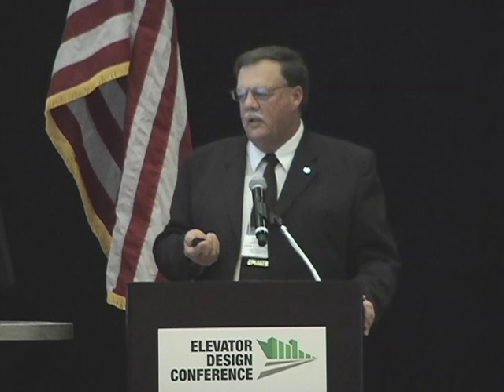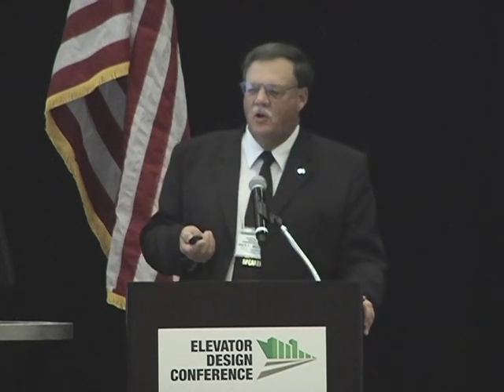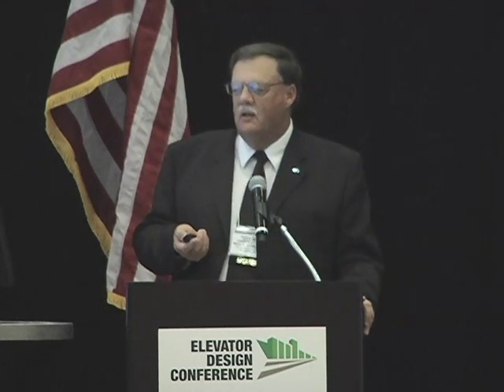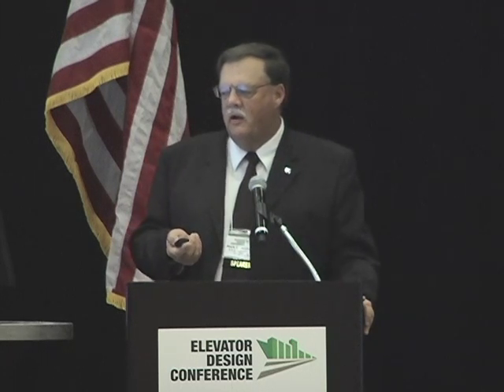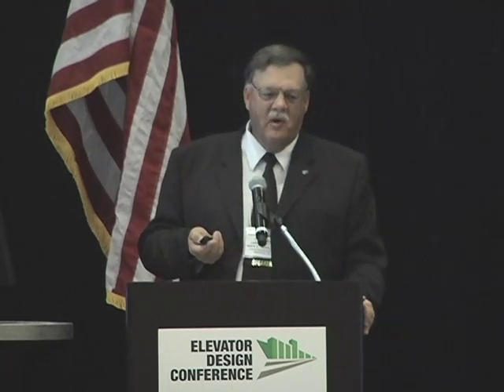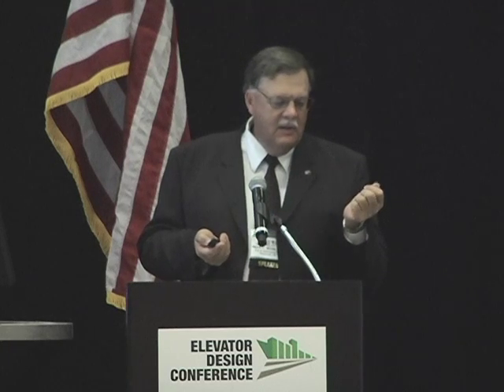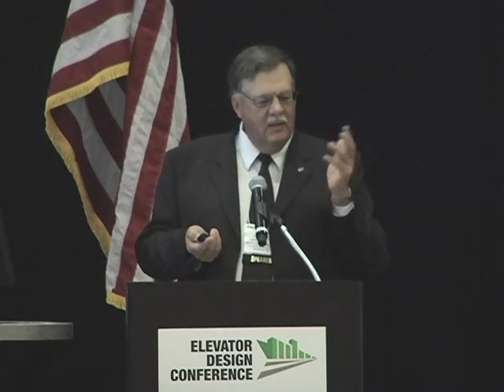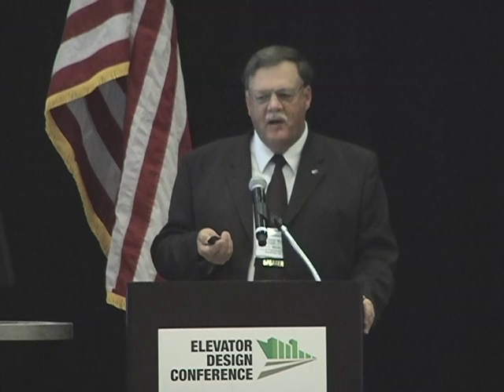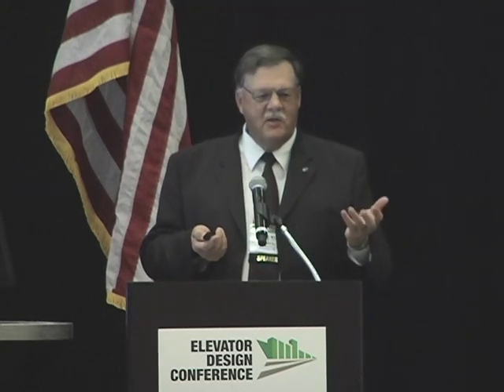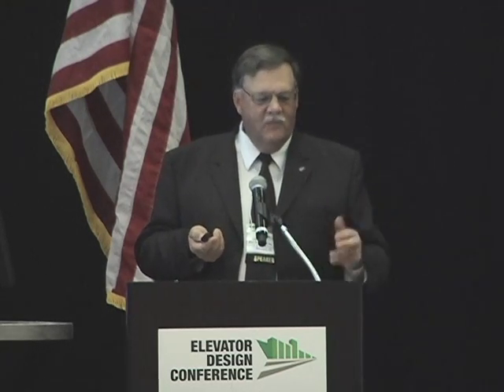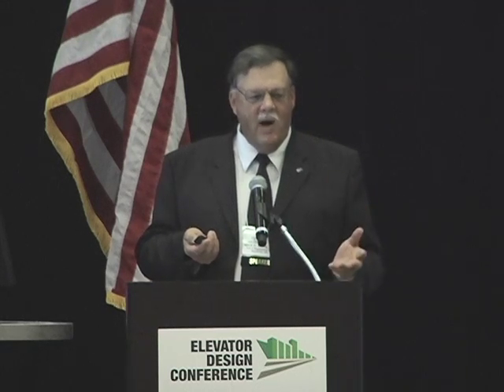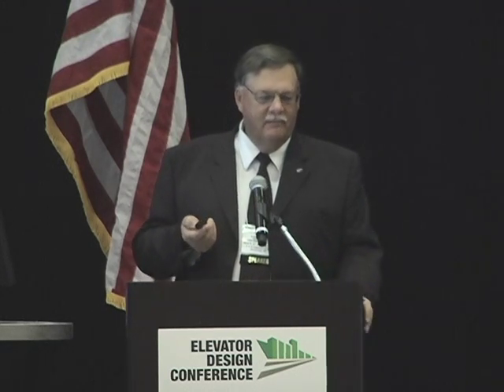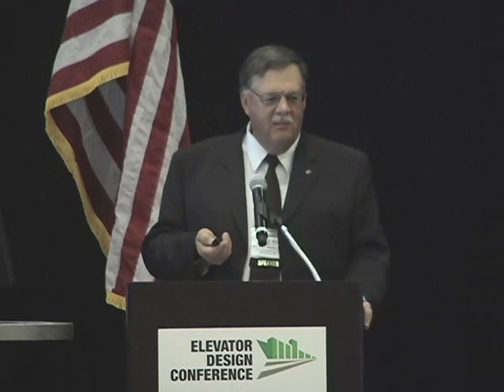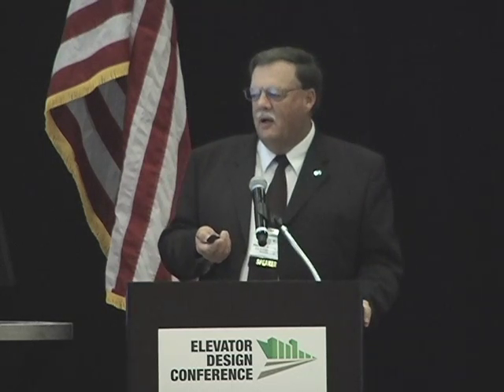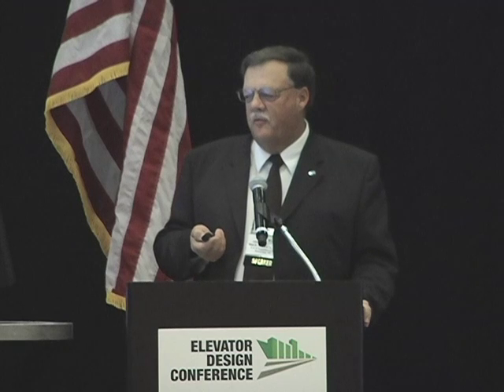Medium voltage systems, like I say, this is only if you get to your really large facilities, typically 4160 or 2400. When you get to the very large horsepower motors, especially when you start getting in excess of 300 or 400 horsepower, all your wire sizes go down. I mean, you can run a 200 horsepower motor on a number 8 wire as opposed to a large 350 kcmil or whatever. It's a big savings in cost and so forth.